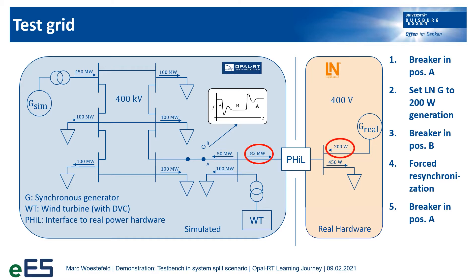Then we will increase the power in-feed from the real generator, which will decrease the simulated load. After we split the system with the breaker in position B, we will force our wind turbine to synchronize our test bench with the simulated generator and we can connect both grids again. So, let's activate the simulation and start the amplifier.